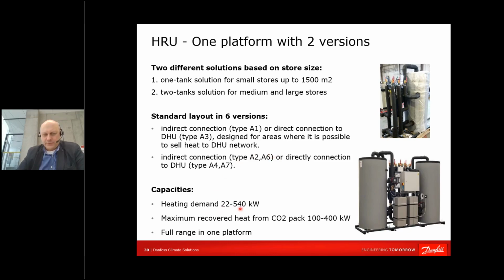Heating demands up to 540 kilowatts. If you browse our data sheets, you will discover these figures. Be aware that these kilowatts were calculated with the estimation that delta T on the plant or building site will be 30, not 10 or 20. And max recovery of 400 kilowatts from CO2.